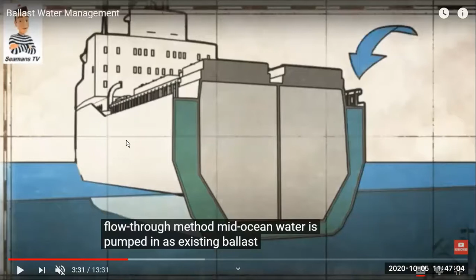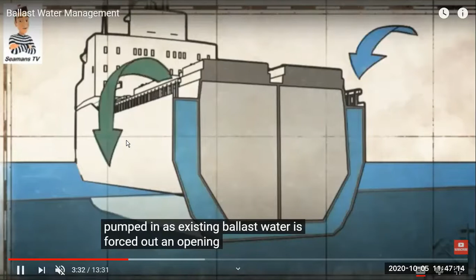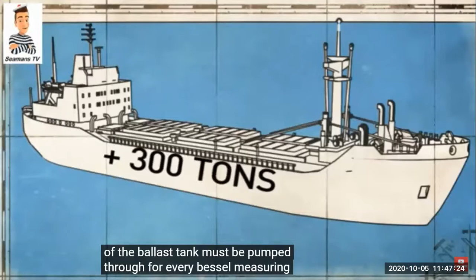Then we have the flow through method. So we keep pumping the tanks with the ballast till 3 times or 300% of the volume is exchanged and forced out of the pumping. So 300% is exchanged, and with that we consider that maximum microorganism changes take place.